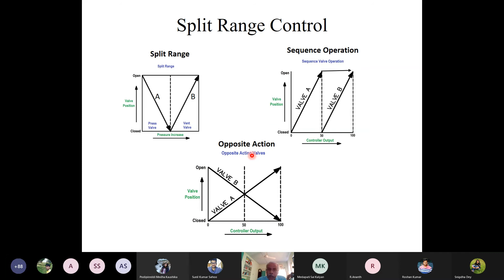If we continue with this control of batch operations, here we can see we have 2 valves. This control valve is fully closed and this one is fully open. Fully closed means that when there is no signal, the control valve is fully closed, and fully open means that when there is no signal, the control valve is fully open. These are also called the fail close (FC) and fail open (FO) control valves.